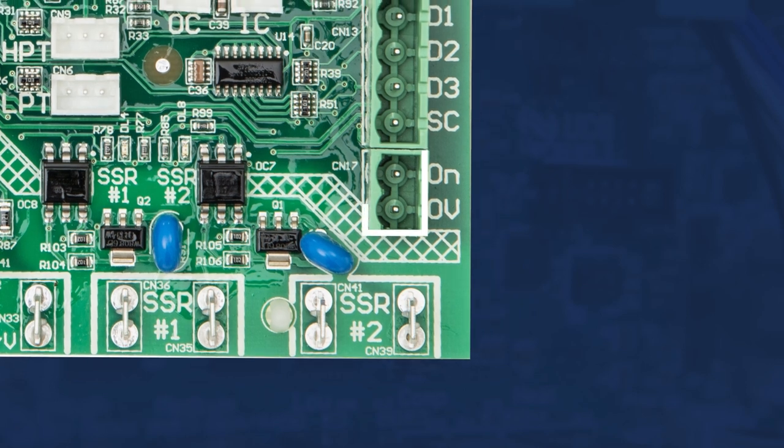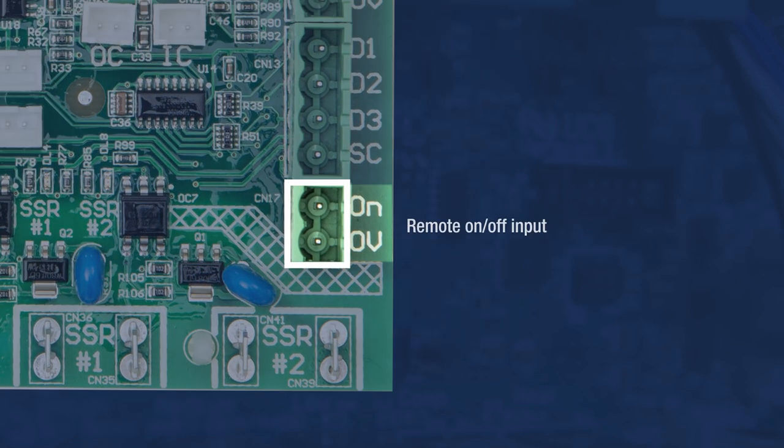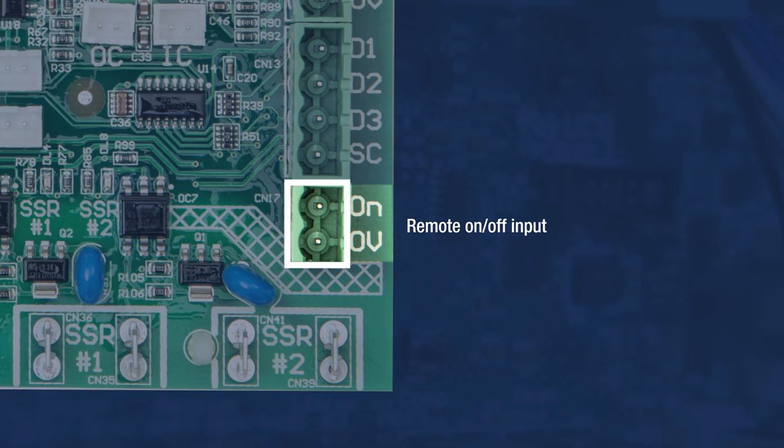The remote on-off terminals are voltage-free terminals that allow for the unit to be turned on and off by external command, such as by a door switch or a room key. Closed loop for on, broken loop for off. This terminal is not capable of a shutdown in fire trip, as the remote on-off function does not interrupt timers such as the fan run-on timer.